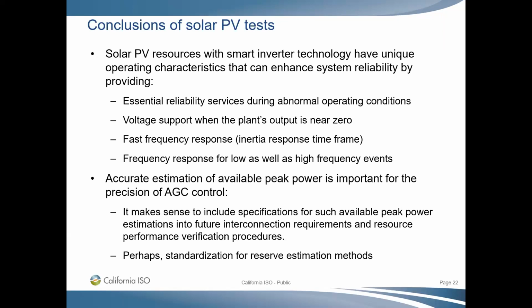And you spoke about frequency response critically. How do you manage a good power factor given rooftop PV systems when gas generation is low? One of the things the federal government implemented, about 3 or 4 years ago, was an order requiring all new inverter-based resources to provide dynamic voltage support. They must provide voltage support, and they need to be able to control a scheduled voltage while operating within 0.95 lead, 0.95 lag at the high side of the transformer bank.